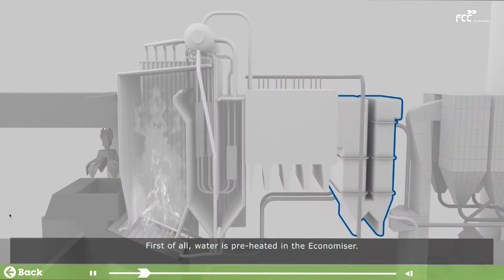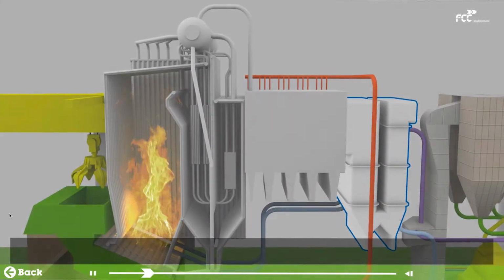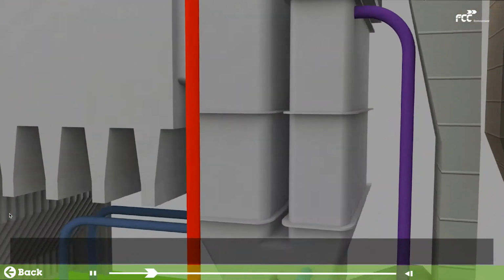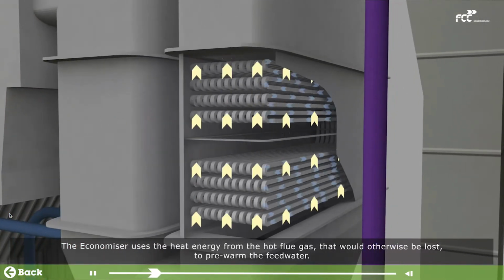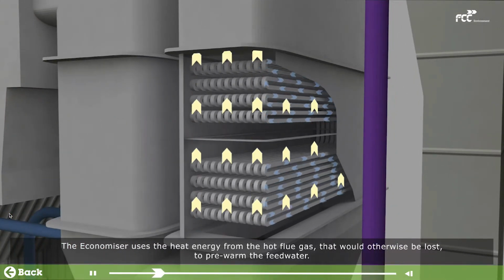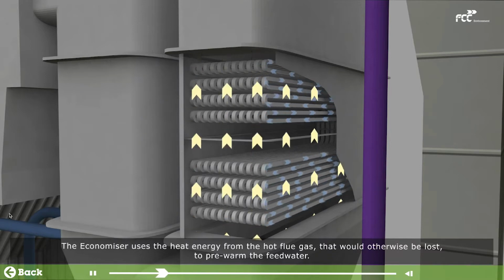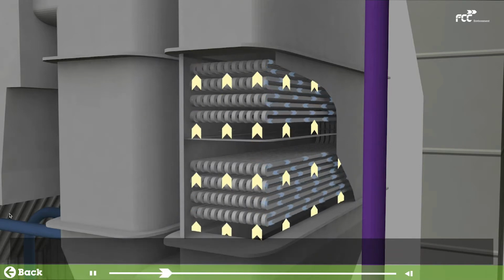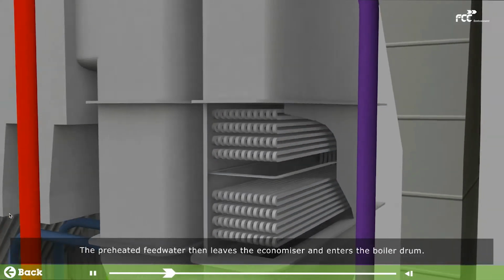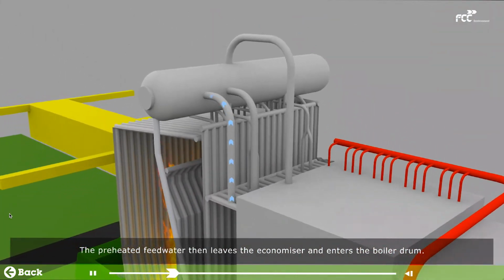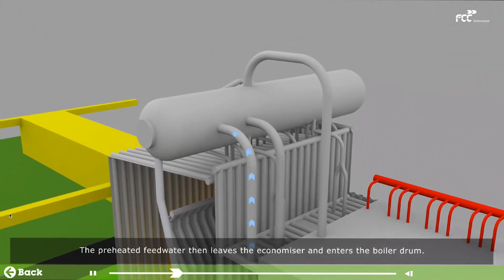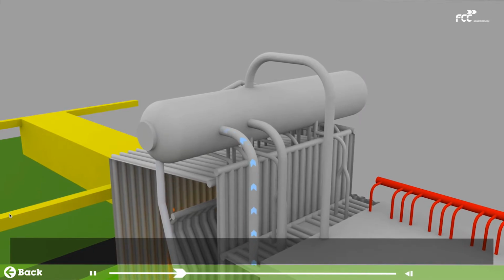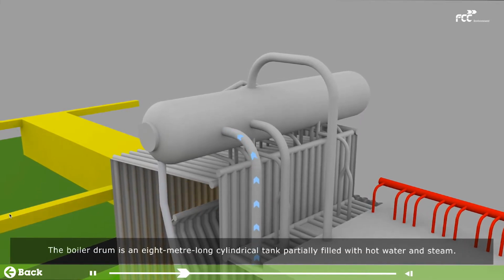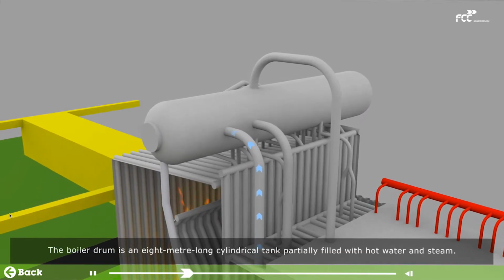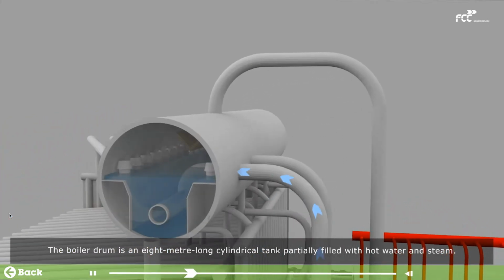First of all, water is preheated in the economizer. The economizer uses the heat energy from the hot flue gas that would otherwise be lost to pre-warm the feed water. The preheated feed water then leaves the economizer and enters the boiler drum. The boiler drum is an 8-meter long cylindrical tank partially filled with hot water and steam.